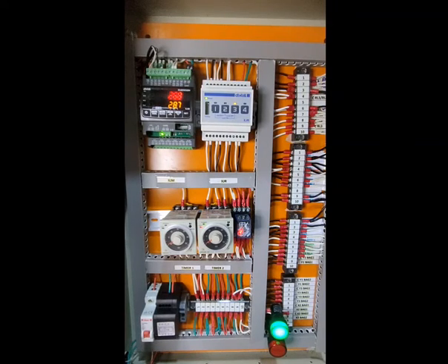Okay, lastly, if it happens that the FDAS of the building is sending an active signal to the control panel, it will shut down the AC units. Right now it's in normal operation. In case of fire, the AC units will be shut down like that.